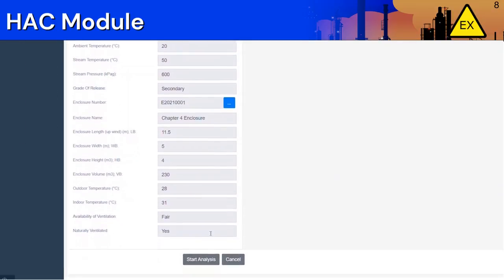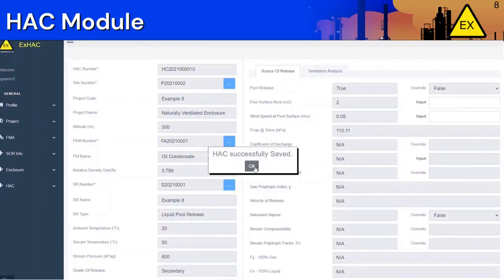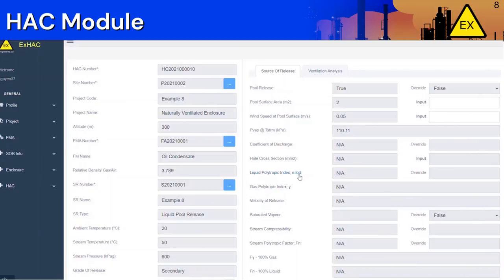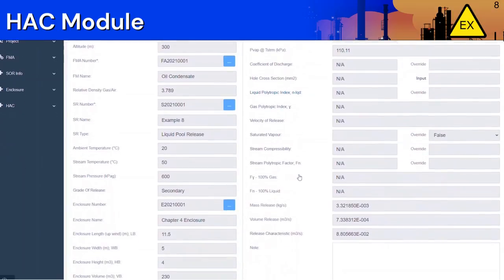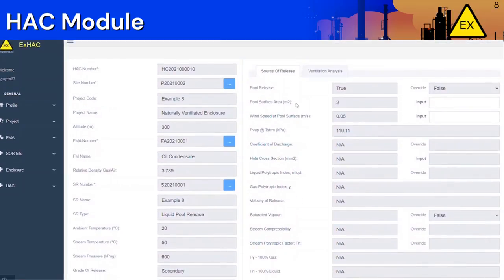Afterwards, the application will calculate some important parameters for you such as the mass release rate and release characteristic. You can also override some parameters such as the pool surface area and wind speed over pool surface if the default values are different for your application. ExHAC has a default value of 2 m² for pool surface area and 0.05 m/s for wind speed at pool surface, but if your project has a different value, you can input it here. Click on Start Analysis again to get the new data, then save your analysis.